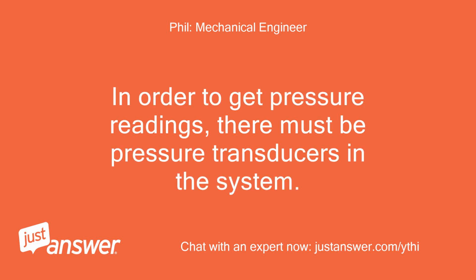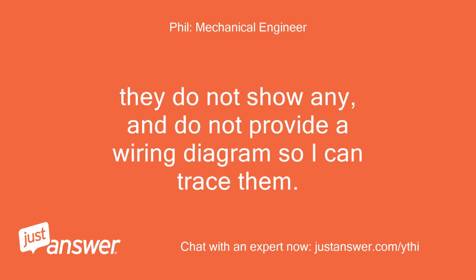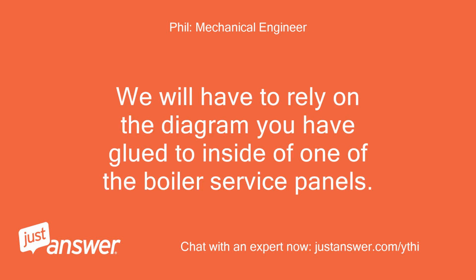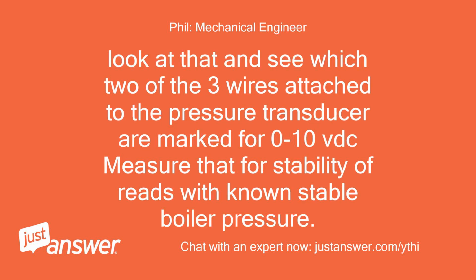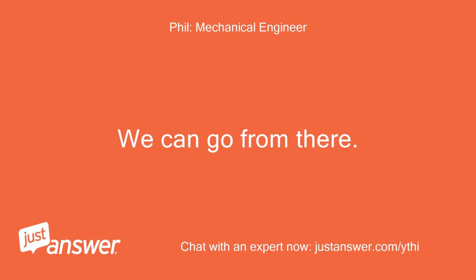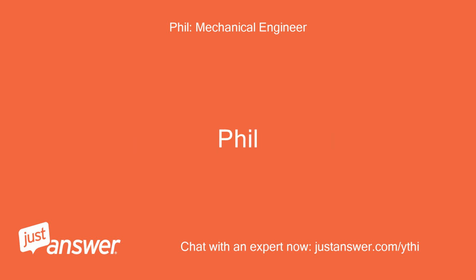In order to get pressure readings, there must be pressure transducers in the system. They do not show any, and do not provide a wiring diagram so I can trace them. We will have to rely on the diagram you have glued to the inside of one of the boiler service panels. Look at that and see which 2 of the 3 wires attached to the pressure transducer are marked for 0 to 10 VDC. Measure that for stability of reads with known stable boiler pressure. We can go from there.